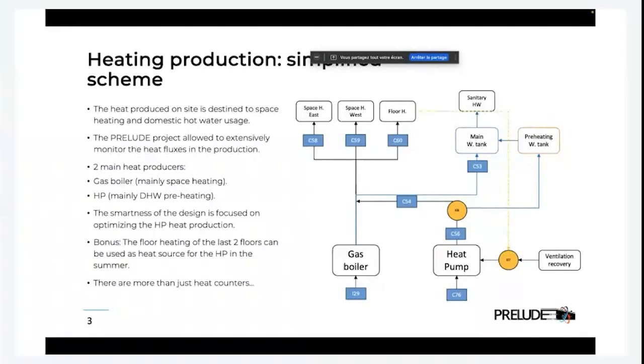Here we use heat for both space heating and domestic hot water. Domestic hot water during the whole year, and space heating for almost half the year. Thanks to the PRELUDE project, we could install a very thorough monitoring of the heat fluxes. On the right you can see the heat fluxes coming from both the gas boiler and the heat pump. The gas boiler focuses more on space heating, with 3 counters covering the space heating of the east and west parts of the refurbished floors, and the floor heating of the last 2 floors. The heat pump produces water for the preheating tank for domestic hot water, and also helps the gas boiler produce heat for space heating.